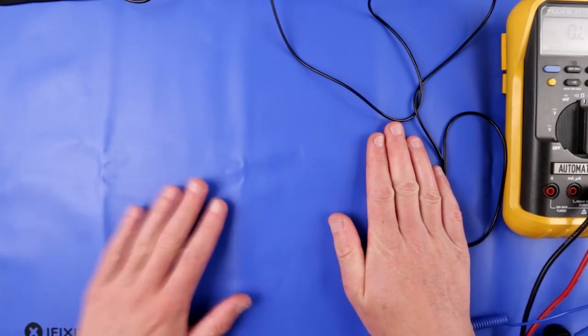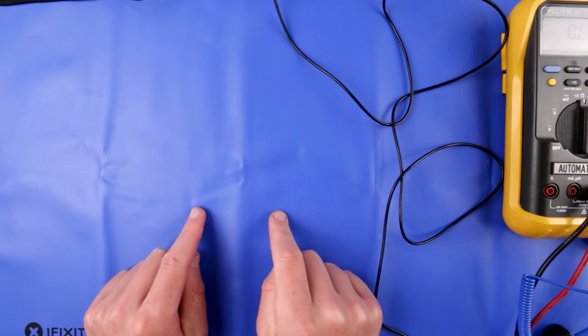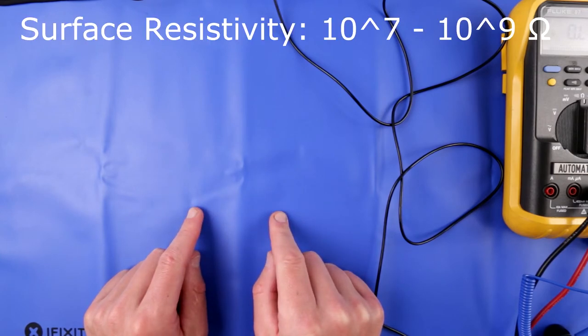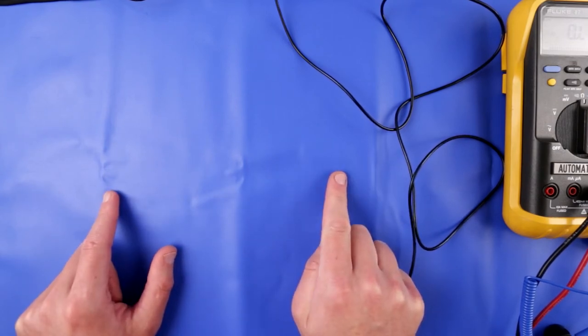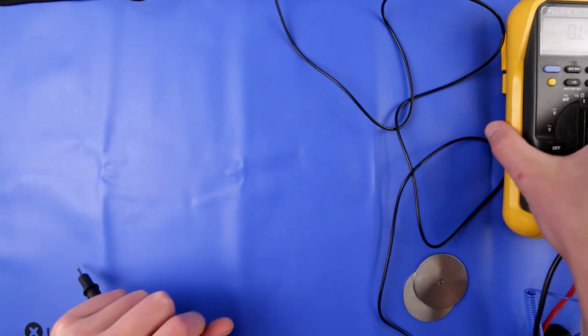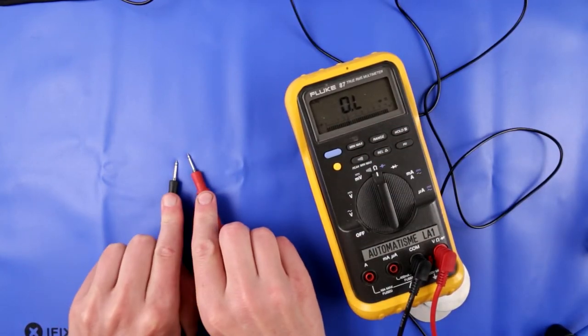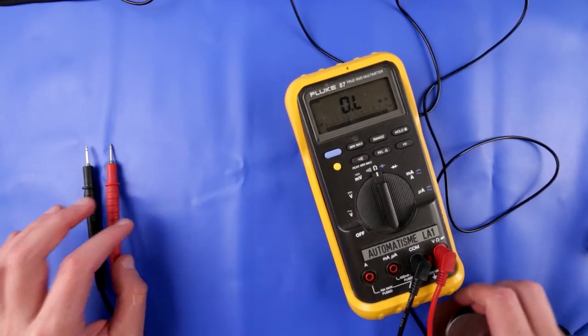Another very interesting thing I would like to do is to check the resistance of this mat. On the box they claim tens of megaohms to gigaohms. There's a whole process for checking and verifying the resistance of these sorts of mats. You have to have dedicated special electrodes, put them at a specific distance - the electrodes have to have specific weight because the electrical contact is important. I won't be able to replicate it exactly, but I have these two things. Doing this with probes does pretty much nothing. You need some electrodes like these.